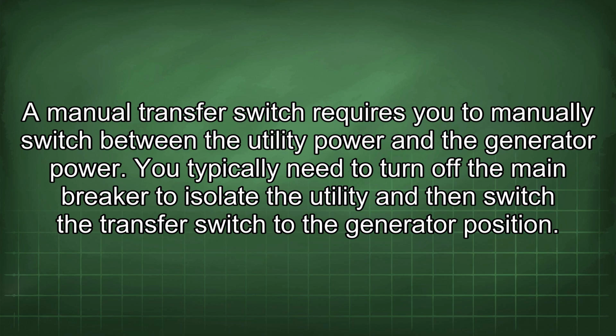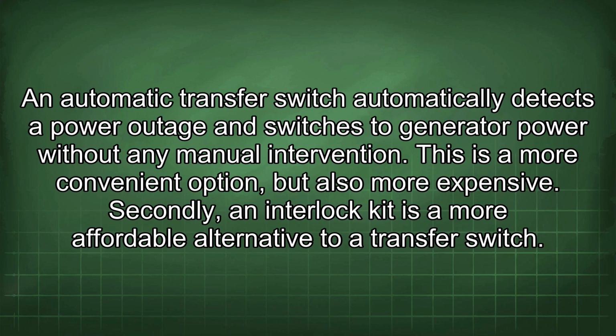You typically need to turn off the main breaker to isolate the utility and then switch the transfer switch to the generator position. An automatic transfer switch automatically detects a power outage and switches to generator power without any manual intervention. This is a more convenient option, but also more expensive. Secondly, an interlock kit is a more affordable alternative to a transfer switch.